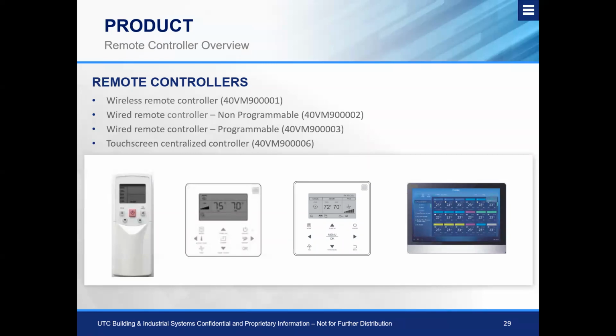Now, for our centralized controllers, if you can see on the furthest right of the screen, this is our most popular style centralized controller. Essentially, it's like a giant iPad, and it's very user-friendly and intuitive. It offers a centralized point where we can get into the system to monitor and record a bunch of different data from a centralized point of view. And this typically becomes handy on larger systems with more than 20 or so indoor units, where we don't have to walk through multiple floors or throughout the entire space to get an idea of how the system's performing or where the issues are in that particular system.